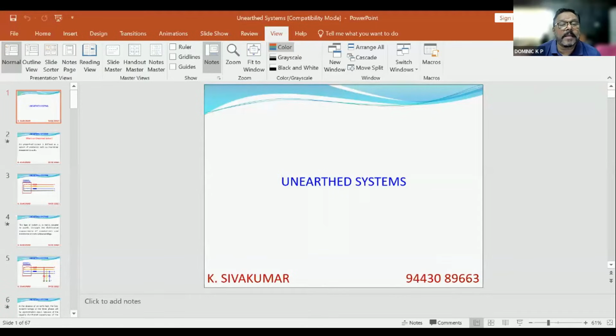Bharat is asking, please advise the right time to check earth resistance value. Sir, there are two approaches. IS 3043 says one thing, and CEA says another. In practice, I would say that every year you please check. It is better to keep a record every year. Once a year, on a dry day, measure the earth resistance. Generally, in my 40 years of experience, whenever I was in charge of electrical installations, we used to measure the earth resistance once a year and keep a record of the same. So I would recommend once a year.